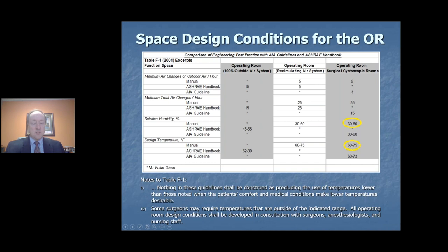Here are the notes and the more current book. Nothing in these guidelines shall be construed as precluding the use of temperatures lower than those noted when the patient's comfort and medical conditions make the lower temperatures desirable. So I see too often that whoever's designing the operating rooms are sticking with these numbers and only those numbers and not paying attention to the fact that that's not really what the doctors want in that particular operating room, particularly the orthopedics and the cardiovascular surgeries.